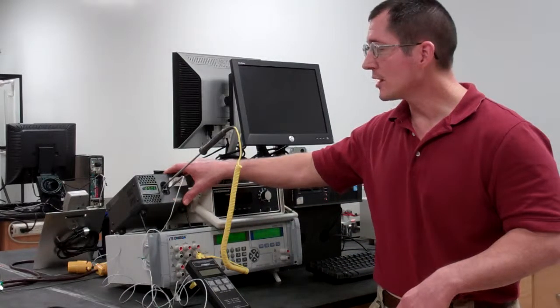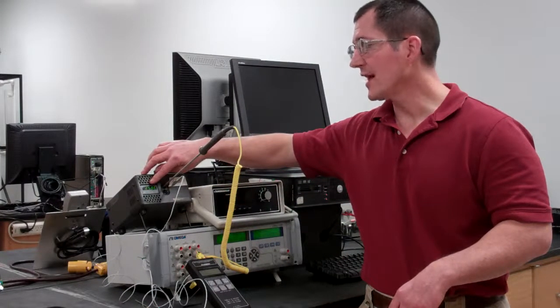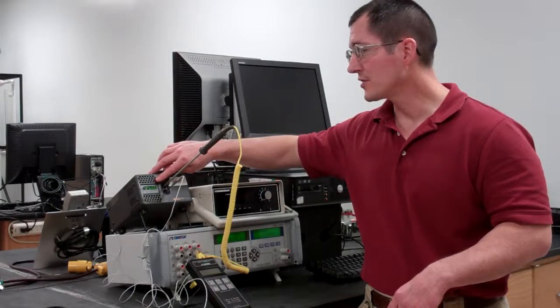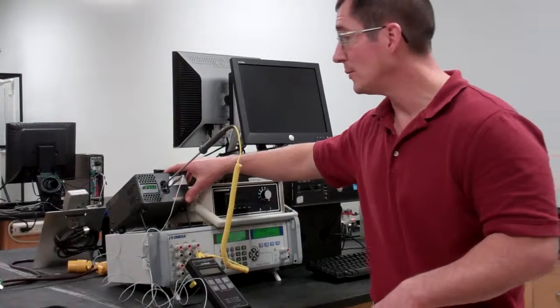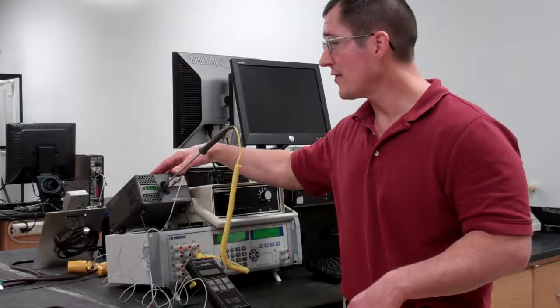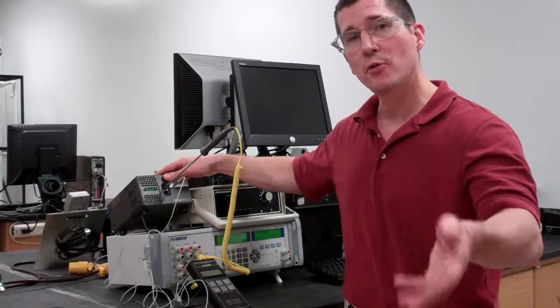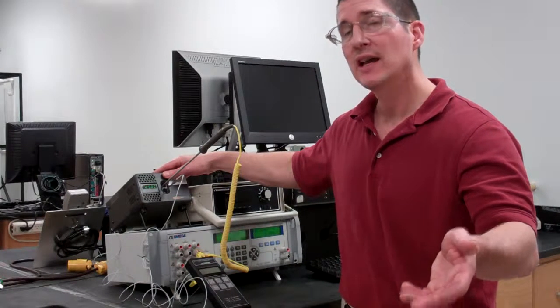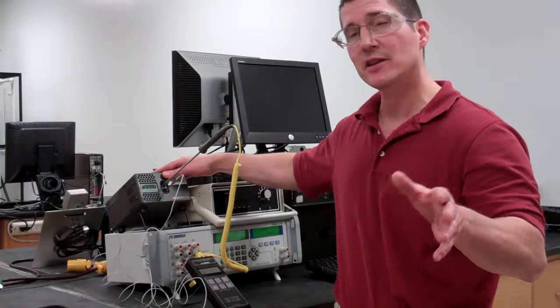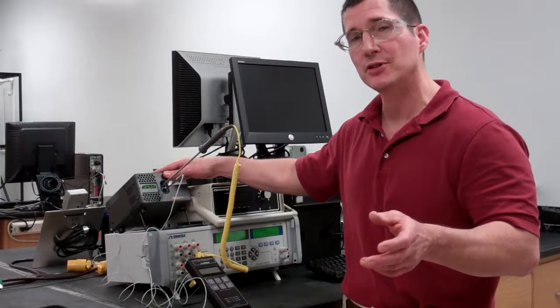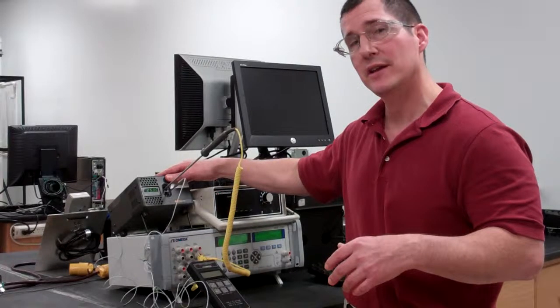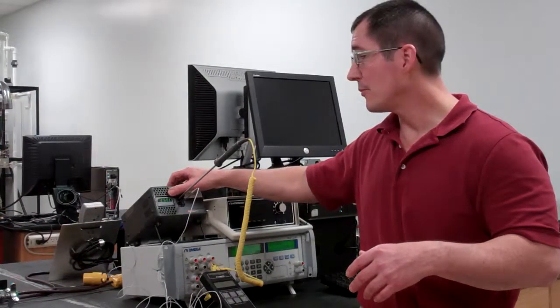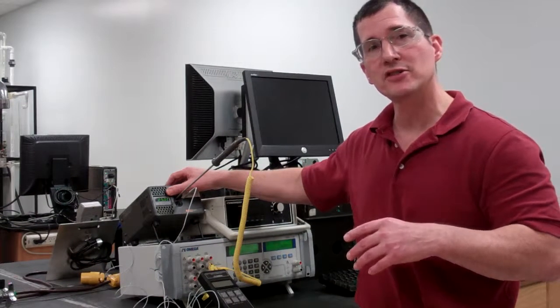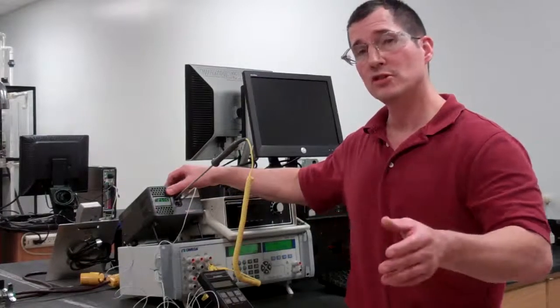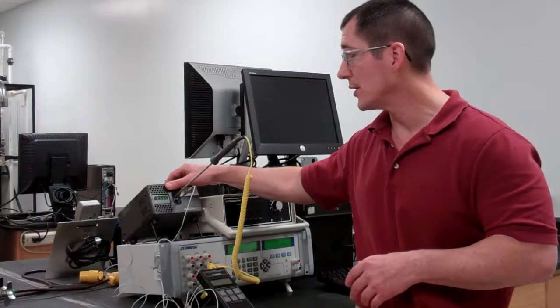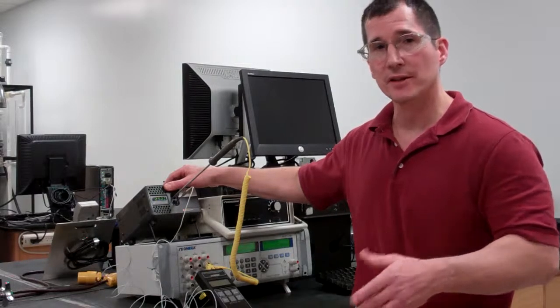We also have a dry block temperature calibrator where I can set a specific temperature. It's important to know that once you set the temperature, it takes time to reach the new set point, and then there's a stabilization time. That limits the number of trials you'll be able to do on this part of the experiment. From ambient to 100 degrees C, or ambient to -10, which is the range of this calibrator, it takes about 10 minutes.